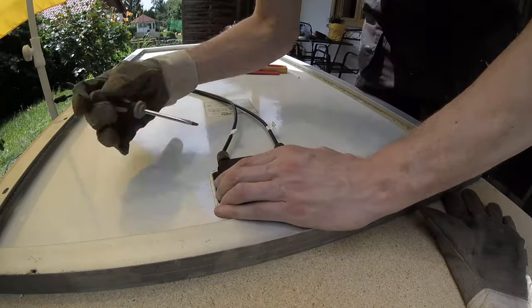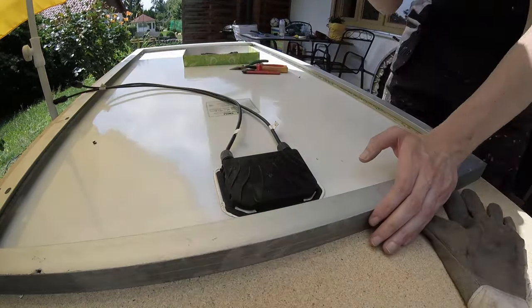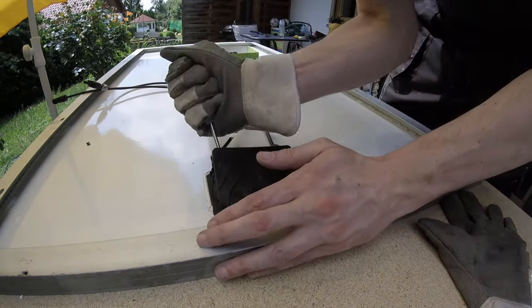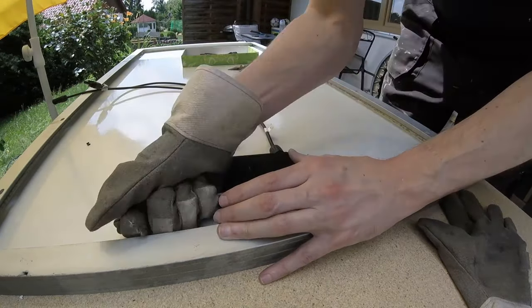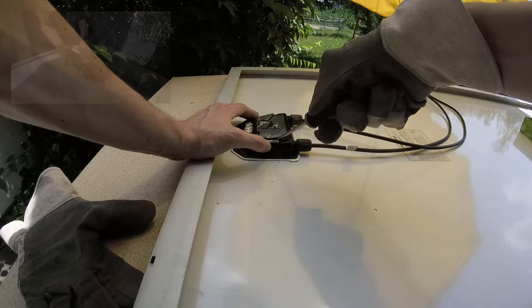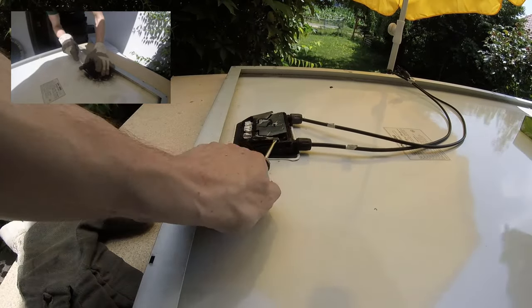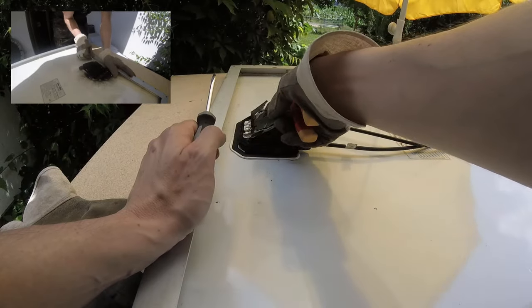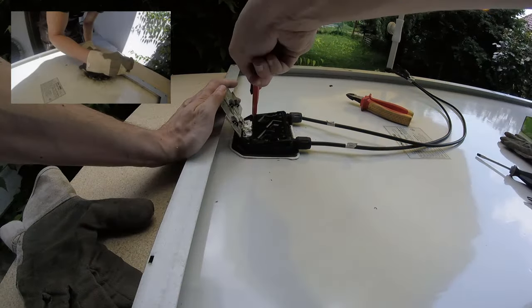First of all, I removed the old junction boxes. These were glued with a lot of silicone to the panel. Because some parts in the junction box were melted, opening them was sometimes a bit challenging. In the upper left corner, I now show you what a burnt panel looks like. It looks like a mess, but the panel worked flawlessly later on.